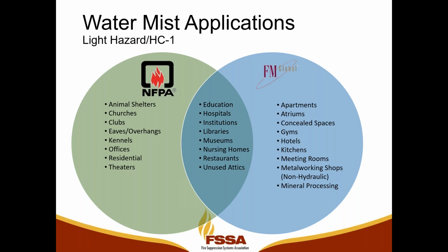So the question would be, and we get this question a lot, can I only protect what I see listed where these circles intersect if I want to be compliant with NFPA and if I want to have an FM approved system? And of course, the answer is no. In both cases, these lists are meant to be representative. They're not meant to be definitive and all-inclusive. They are meant to give you examples of the types of spaces that fit within the FM definition and that fit within the NFPA definition. NFPA 13 specifically leads into their definition of light hazard with the words "include spaces with uses and conditions similar to." So that tells you that this is a representative list.